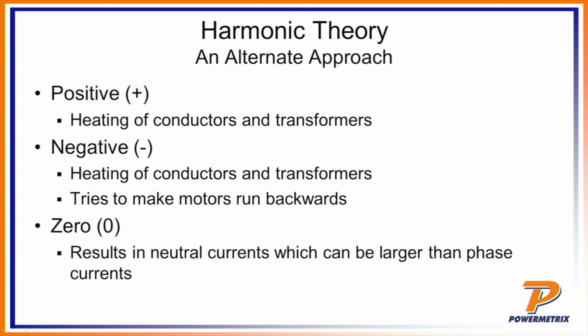So once again, in summary, we can look at harmonics as either positive, negative, or 0. Positive can cause heating of conductors or transformers because it's trying to push that motor to run a little faster. Negative harmonics can also cause heating of conductors for the same reason but slowing it down. And 0 can result in neutral currents that can be larger than the phase currents, once again causing overheating or even fires.